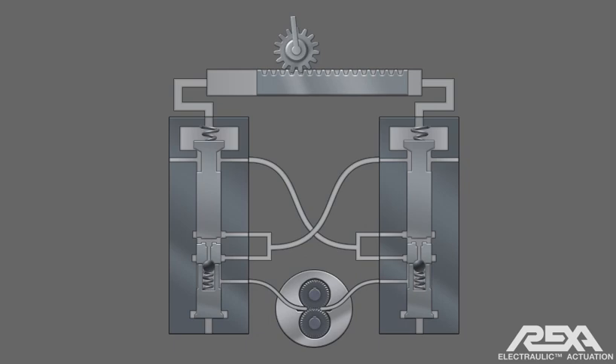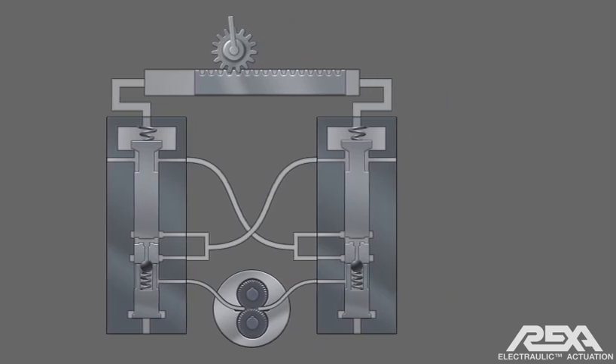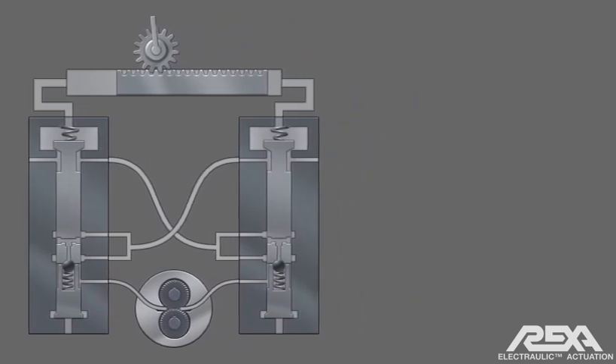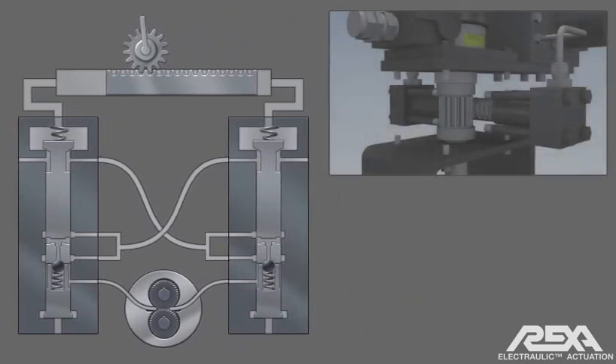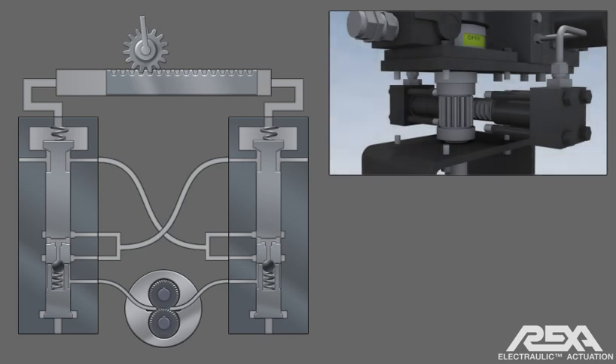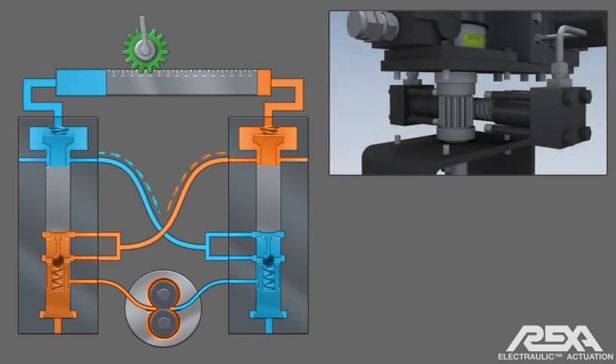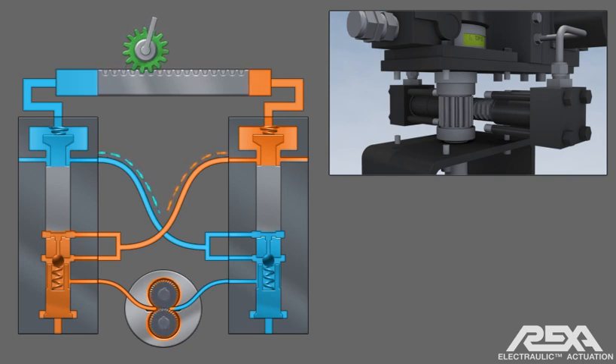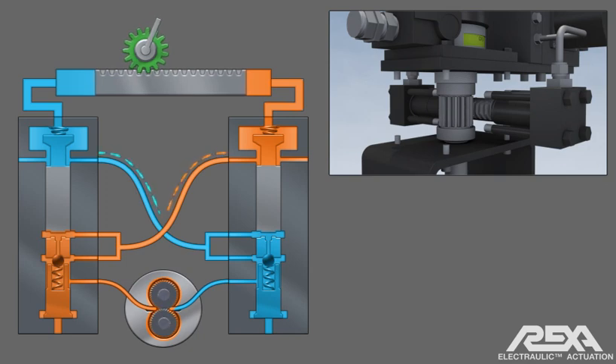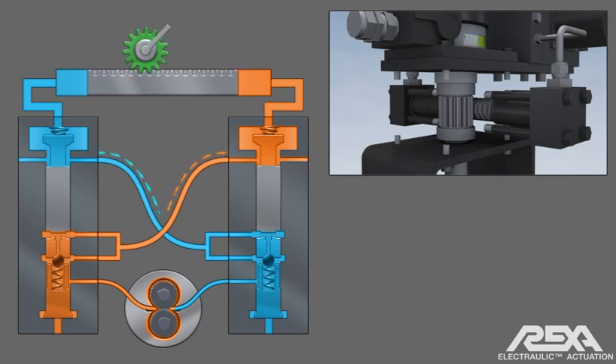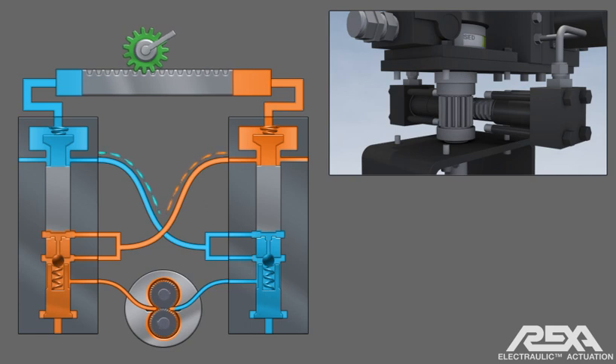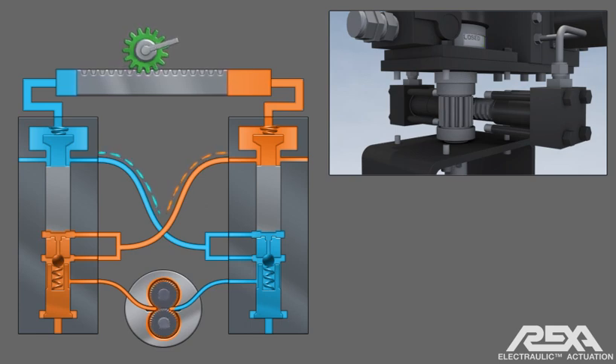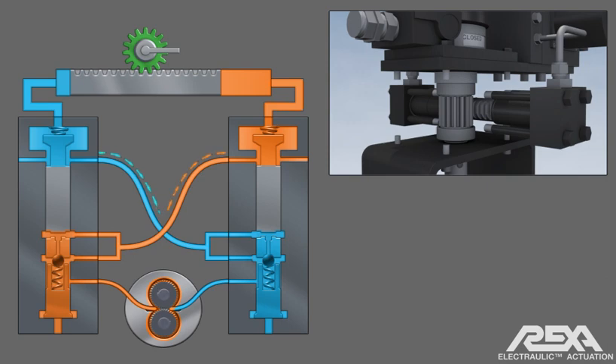In this instance, the main valve is required to close. The hydraulic pump will start, simultaneously supplying the bottom chamber as it draws from the top chamber. The top chamber is the supply for the bottom chamber and vice versa when the pump direction changes. The pump will displace the oil, simultaneously lifting the flow match valve spools and aligning the ports depending on the direction of rotation of the pump. The actuator will move the connected valve in the direction that the cylinder drives it based on from or to which side of the cylinder oil is being transferred.